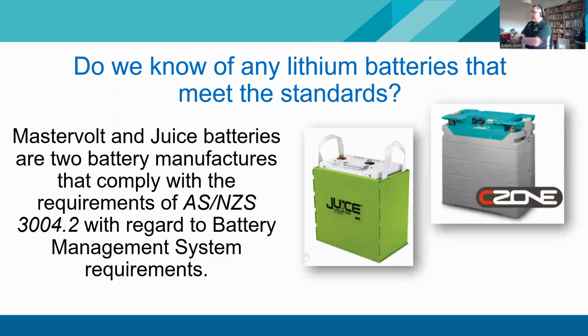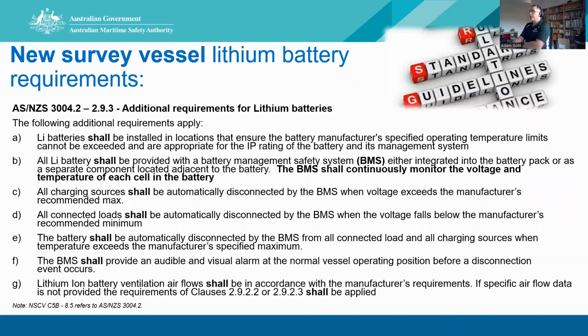We know these two batteries meet the standards. We're not advertising. We don't advertise any particular brand over any other, but out of interest, these ones do. AS/NZS 3004.2 on a new vessel, you've got the added standard guidance, which is 2.9.3. So part A, we've got lithium batteries shall be installed in locations that ensure the battery manufacturer's specified operating temps cannot be exceeded and are appropriate for the IP rating of the battery and its management system.